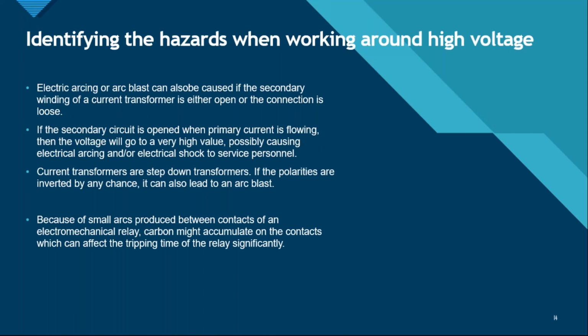Because of small arcs produced between the contacts of an electromechanical relay, right? An electromechanical relay can detect the current, and it has metal contacts which give a signal to the circuit breaker to trip it open. If those contacts are not cleaned because of those sparks, those minor arcs, there might be carbon accumulated on the contacts.